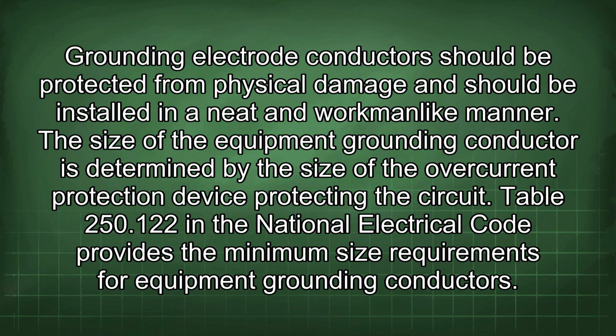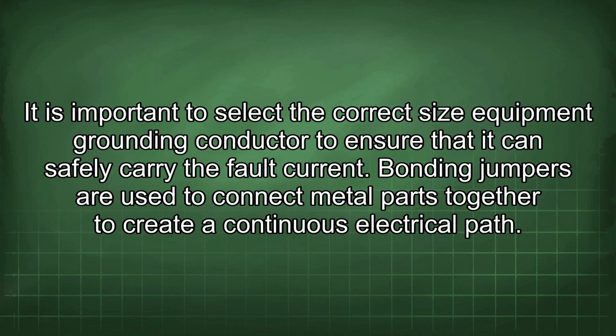The size of the equipment grounding conductor is determined by the size of the overcurrent protection device protecting the circuit. Table 250.122 in the National Electrical Code provides the minimum size requirements for equipment grounding conductors.